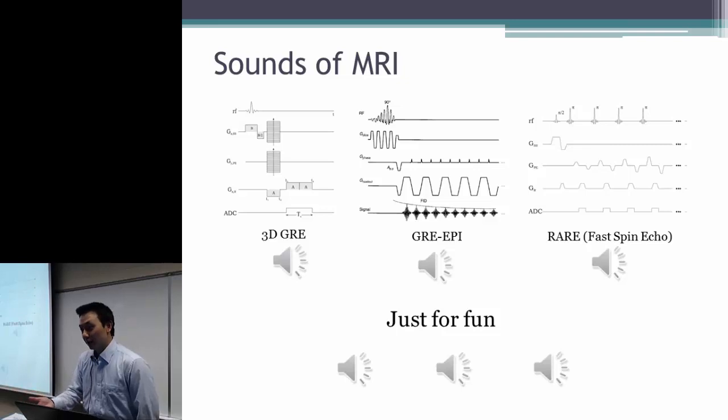To create a gradient, we need to give the gradient coils different levels of current, those alternating currents. So the gradient coil is now like that wire in the magnet. It is also seeing the magnetic field, so it will also be vibrating. So that's the vibration of the coils.